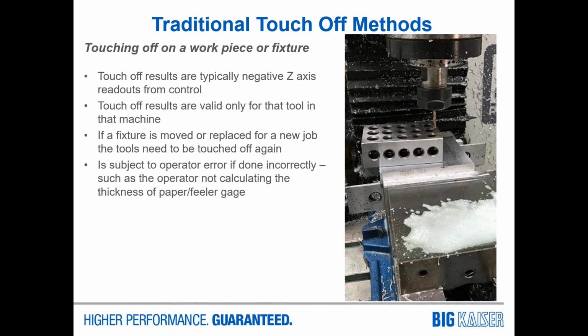These traditional touch-offs can have their own problems. For example, the paper method, where a machinist grabs a piece of notebook paper or a sticky note—or my personal favorite, a cigarette rolling paper—and uses the same idea as the gauge block, slowly shimmying that paper underneath the tool while jogging it down until the paper stops moving. The problem is that paper thickness can vary by a matter of thousandths. Once the paper stops moving, a lot of people just look at the Z-axis readout and take that as their number. Some people account for the paper thickness, but often it's a guess, so you could be anywhere from 1 thou to 3, maybe 5 thou off from your actual tool offset. It's an inherently less precise way of measuring tools.